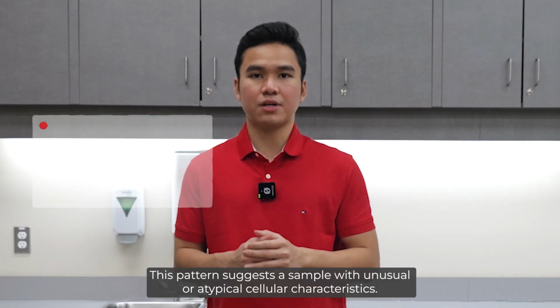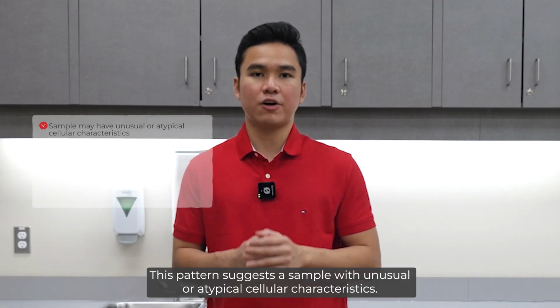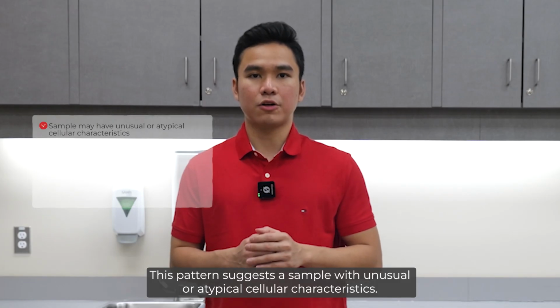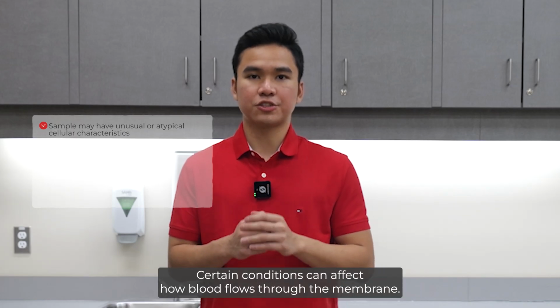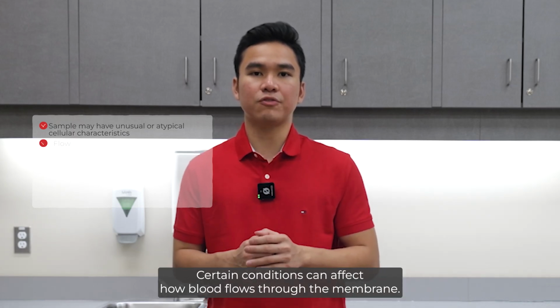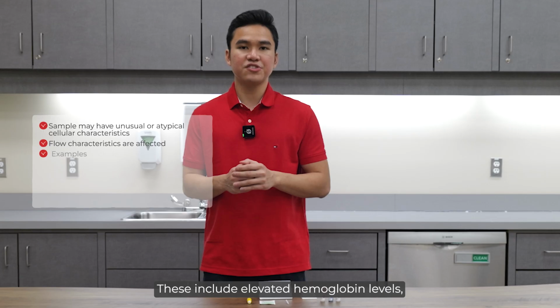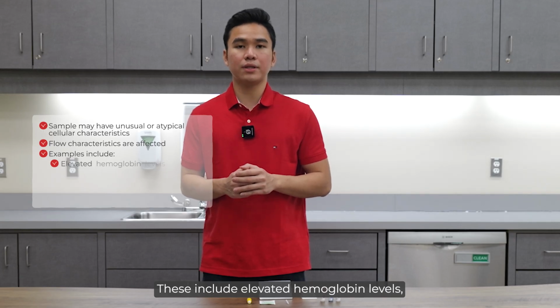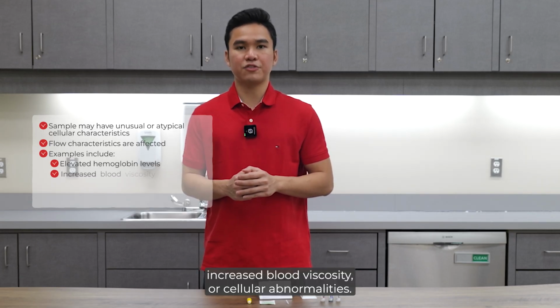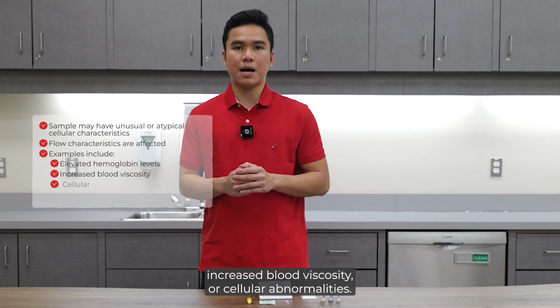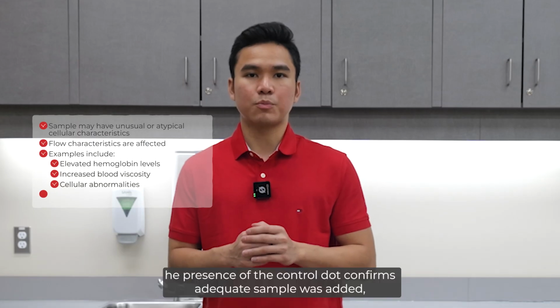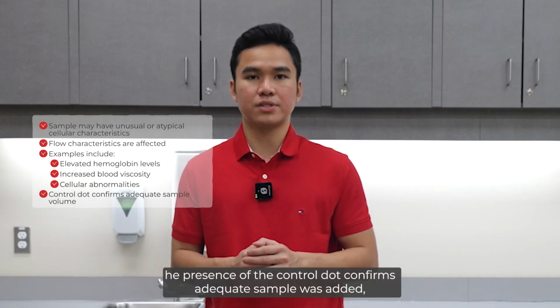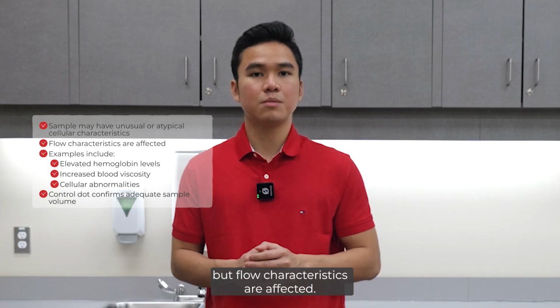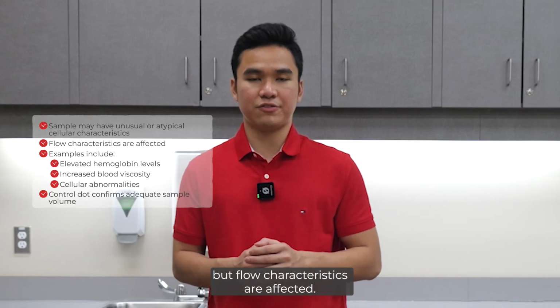What's happening? This pattern suggests a sample with unusual or atypical cellular characteristics. Certain conditions can affect how blood flows through the membrane. These include elevated hemoglobin levels, increased blood viscosity, or cellular abnormalities. The presence of the control dot confirms adequate sample was added, but flow characteristics are affected.